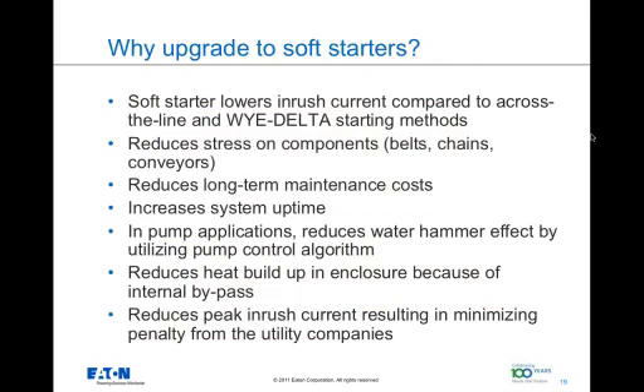Now let's come to the key question of why we need to upgrade to soft starters. The first four bullet points here are the ones we have discussed so far, the first being that by using a solid-state soft starter, you are reducing the amount of inrush drawn into the system, and as a result, the stress on the components is reduced. You're increasing the system uptime and system life, and you're reducing the maintenance costs that go into the upkeep of the system.